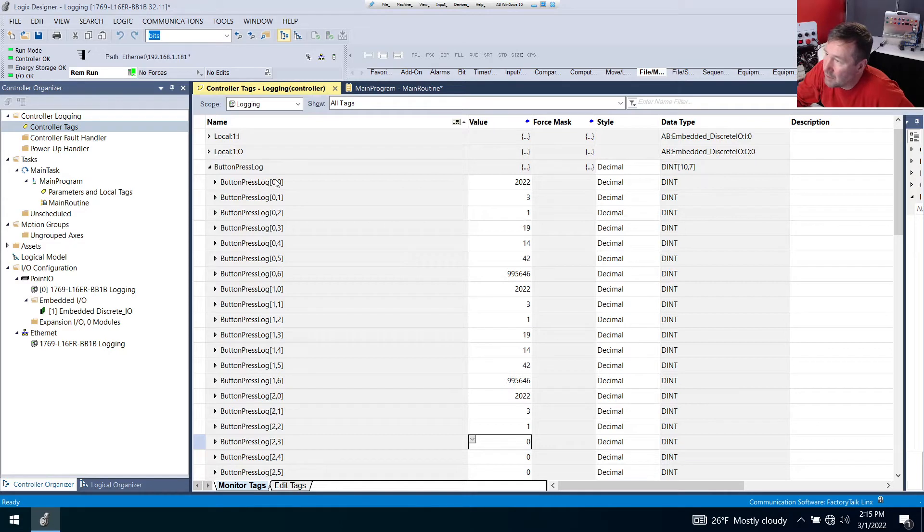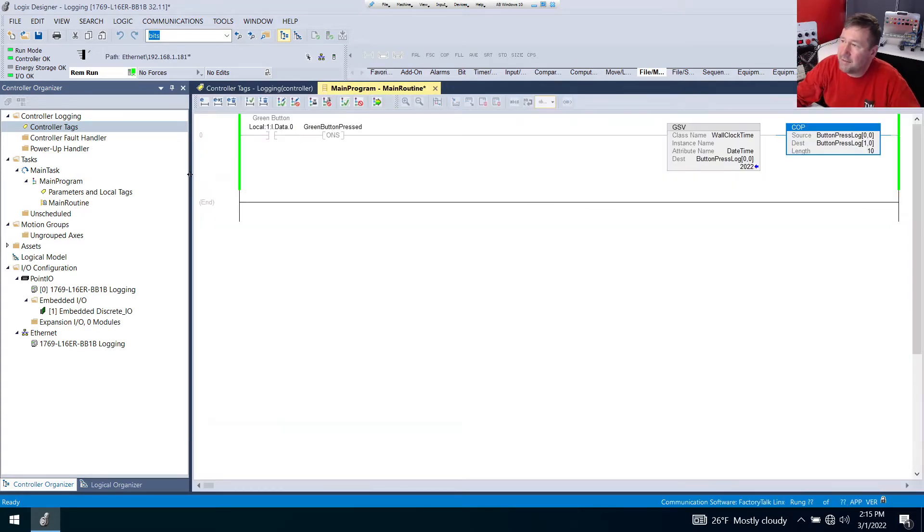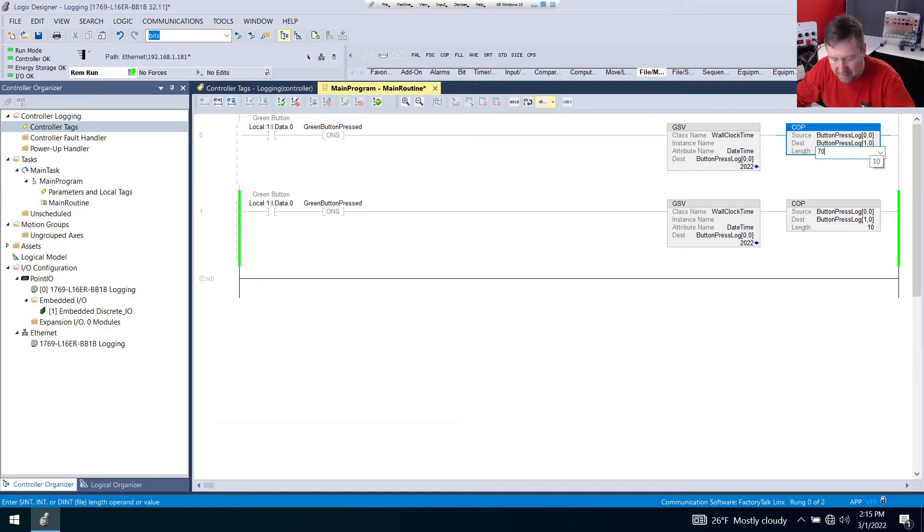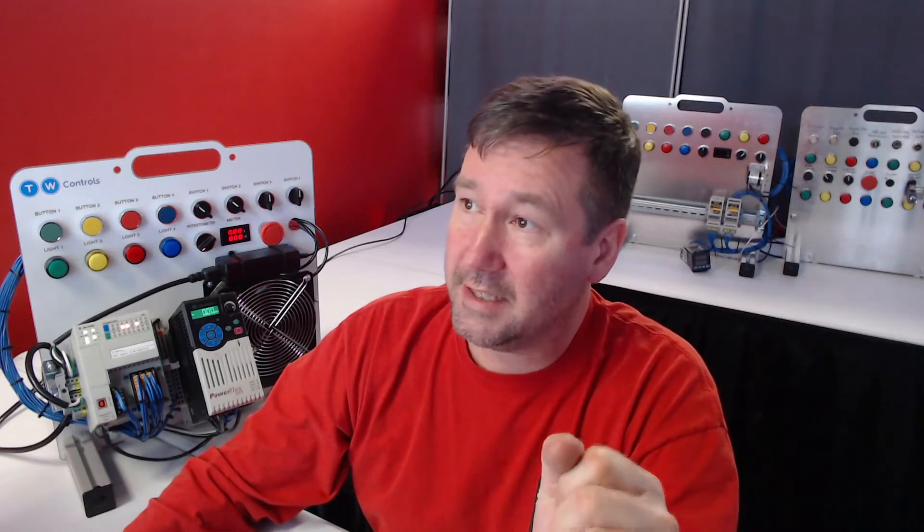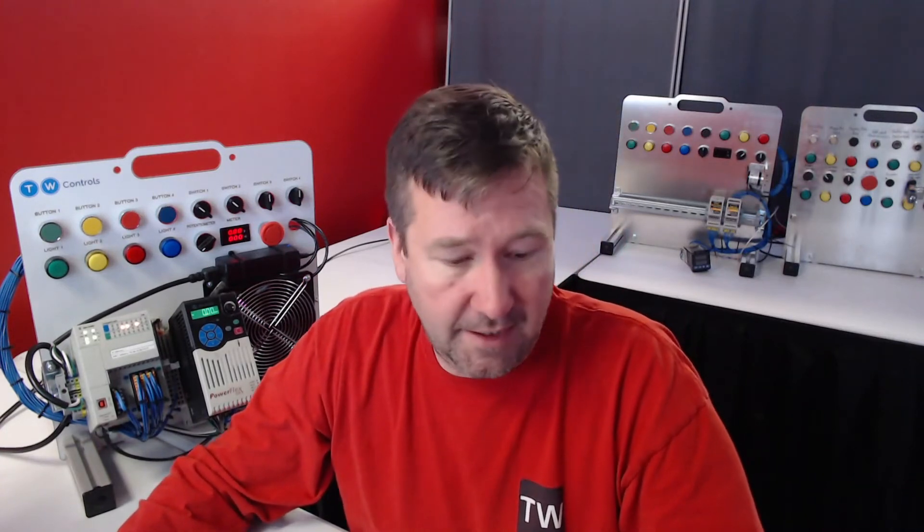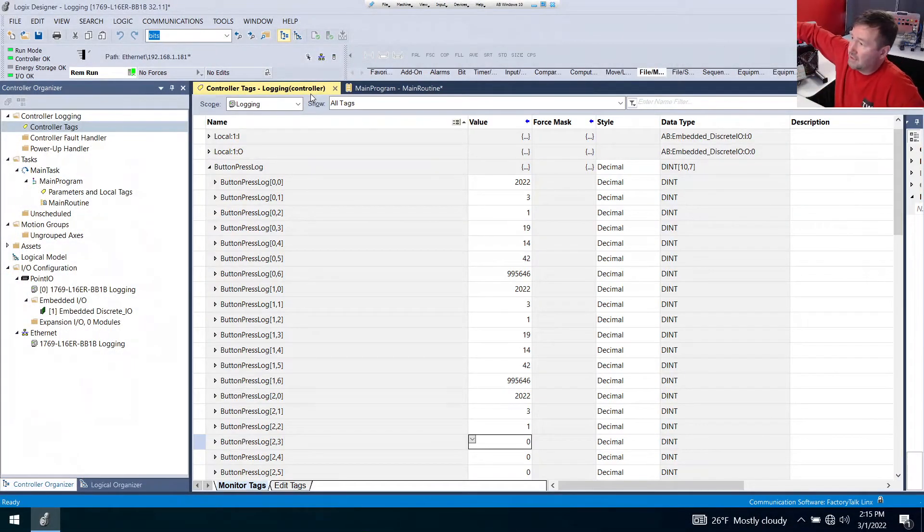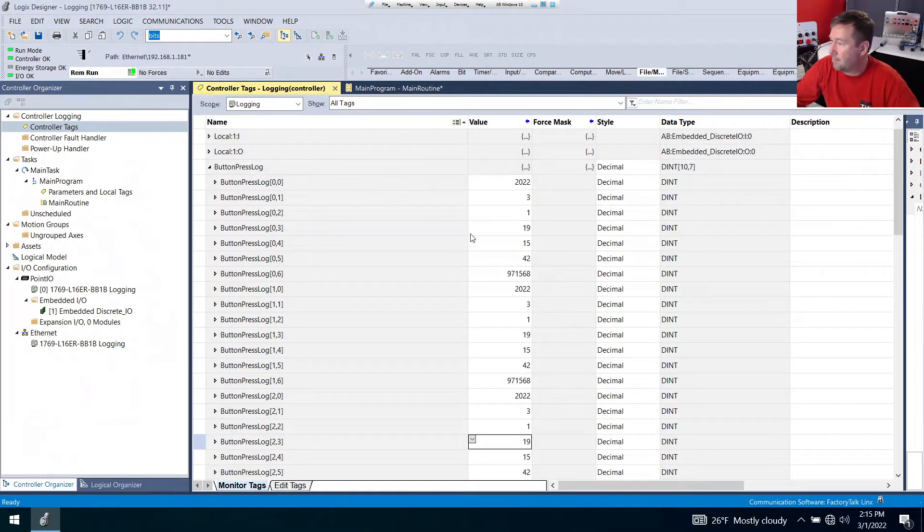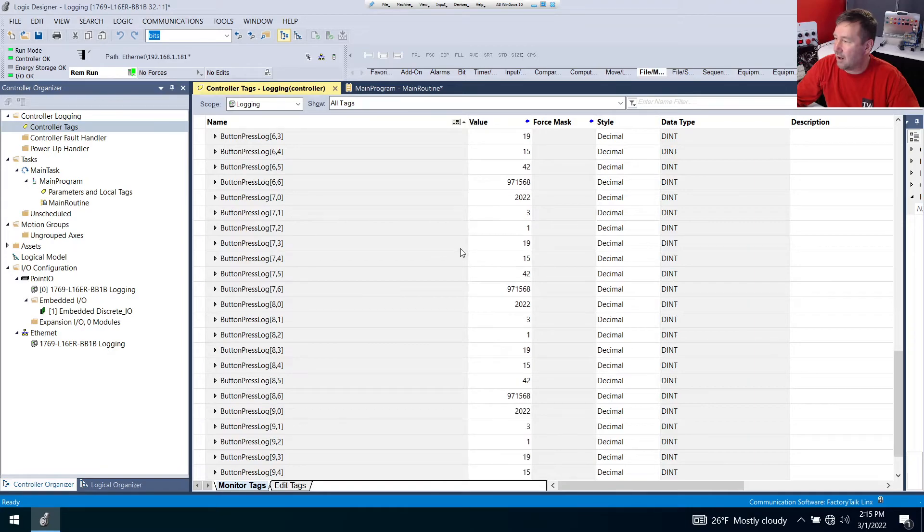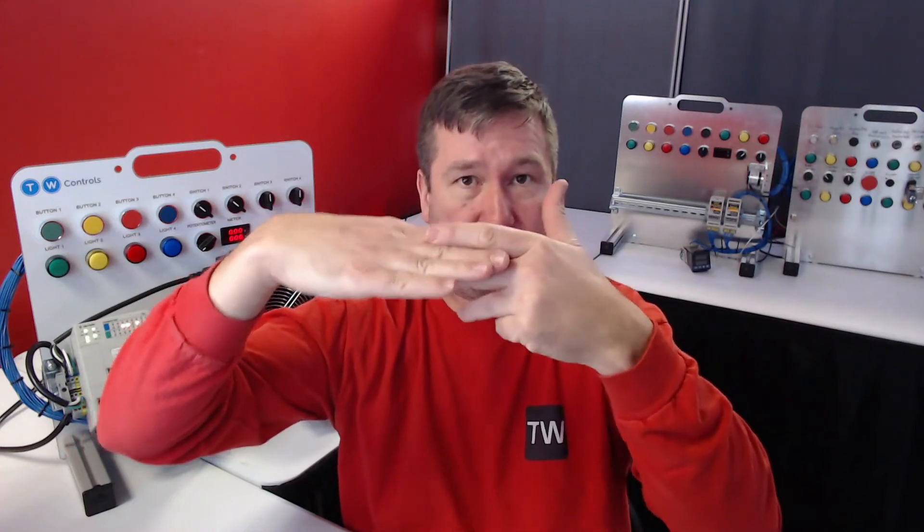So what we need is the actual number of elements here. So we have 7 one way and we have 10 the other way for a total of 70 elements. So what we're going to do is we're going to change our length to 70. Now just in case you're keeping score, we are still on the wrong way to do this guys, but I want to make sure we understand exactly what is going to happen here. So now I'm going to go back over to my controller tags and I'm going to press the green button and bam, right away we have the exact same value in all of these.